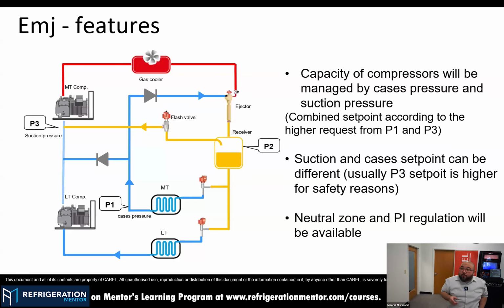And so the capacity of the compressors will be managed independently by these two different probes, P1 and P3, and we are always making sure that we are satisfying pressures on both ends. For example, depending on the type of system, my MT load could go to defrost, so I don't have a requirement from MT cases or evaporators, and I still have load from LT. I can keep my pressure running because I have a P3 probe looking at the pressure at the discharge LT and suction MT, making sure that line is also satisfied. So we have a lot of internal logic to protect it.